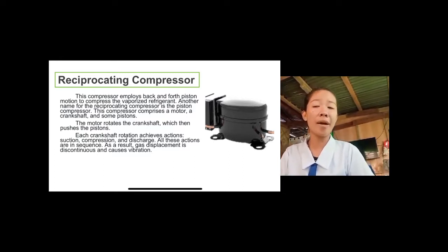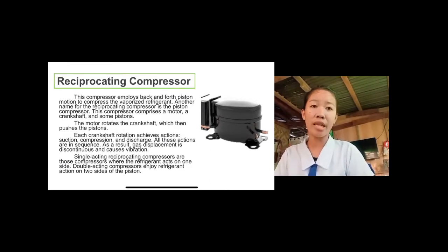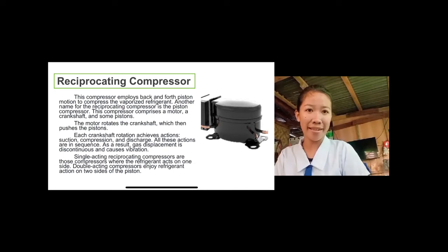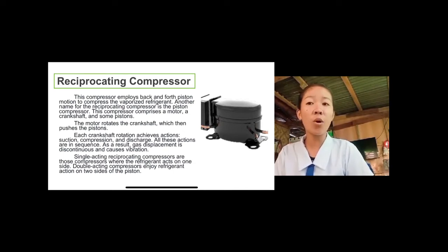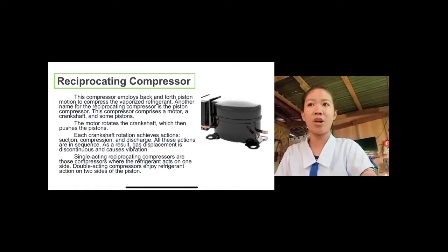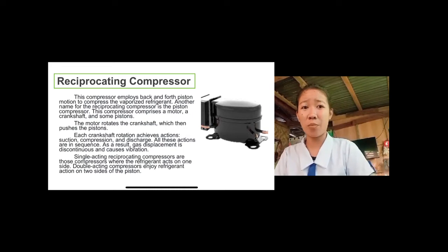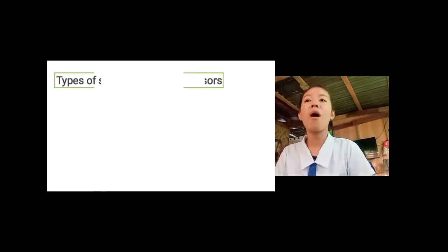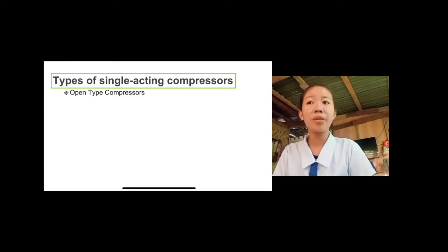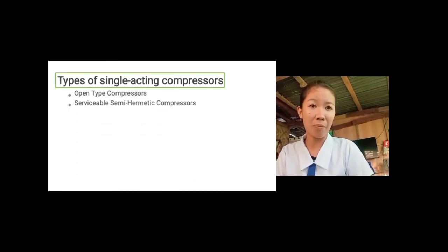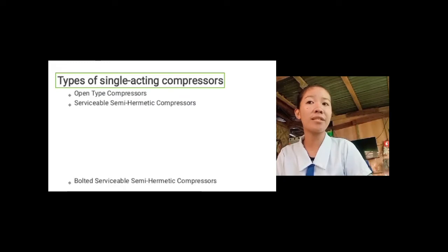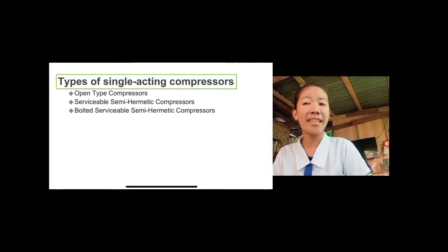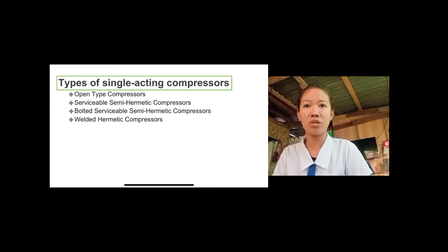So there are two types of reciprocating compressors. One is the single acting reciprocating compressor, where the refrigerant acts on one side. The other is the double acting compressor, with refrigerant action on two sides of the piston. What are the types of single acting compressors? There are four types. One is the open type compressor. Two is the serviceable semi-hermetic compressor. Third is the bolted serviceable semi-hermetic compressor. And lastly, the welded hermetic compressor.